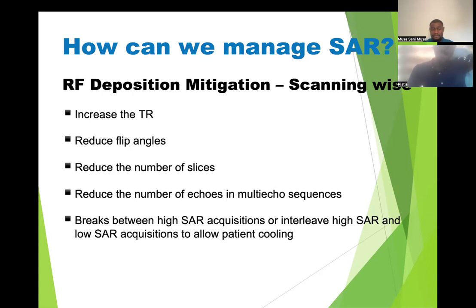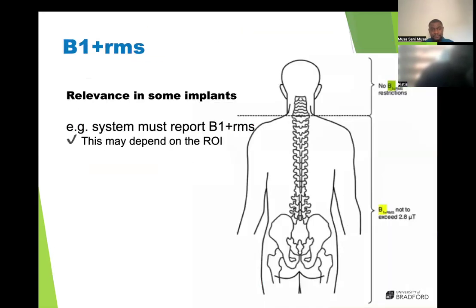If you're scanning a patient with certain implants, in order not to overheat the patient, after scanning one sequence you can give them a cooling break for the body to return to normal body temperature before you proceed to the next sequence. It's another way of managing SAR. So this is B1 plus root mean square. Like I said, this one has nothing to do with the body weight. It's got to do with certain types of implant, and it also relies on the region of interest.